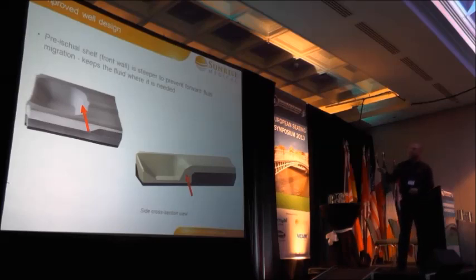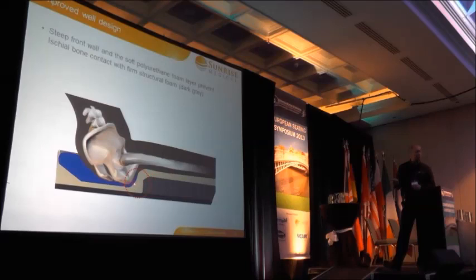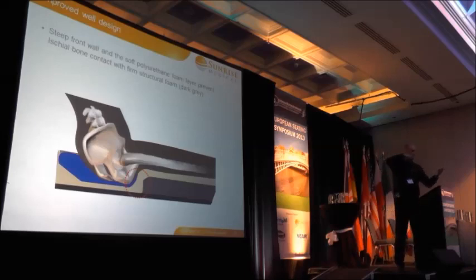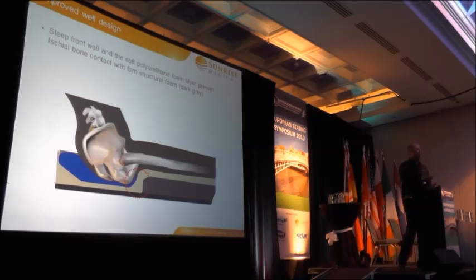However, it has to be carefully applied. With that steeper front wall, we've got to be careful that when the pelvis drops back into posterior pelvic tilt and the ischials do come forward, we don't load the ischials onto the front wall of the dish. With the J-Balance cushion, though, there is such a thick amount of foam that if you were to push your knuckles against the front wall, you physically can't reach the very firm layer at the bottom — so it has that added protection if a person does move into that position.